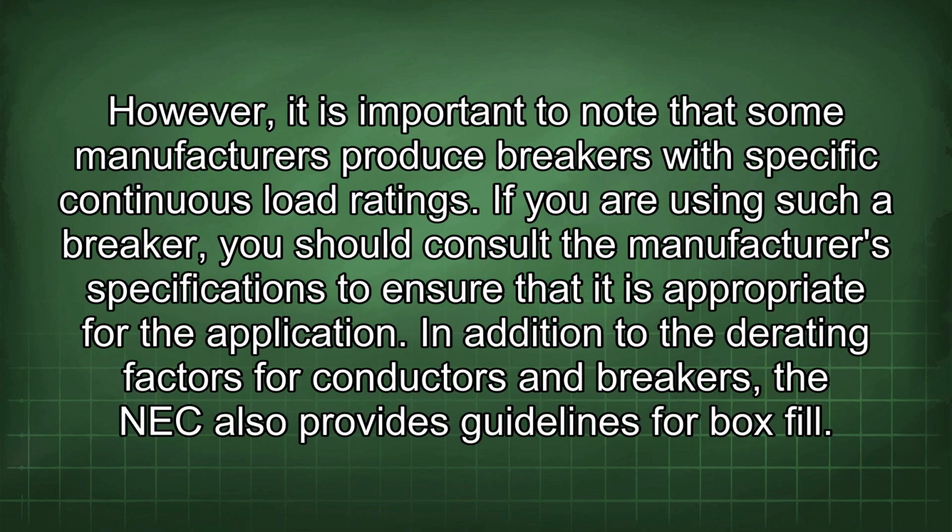However, it is important to note that some manufacturers produce breakers with specific continuous load ratings. If you are using such a breaker, you should consult the manufacturer's specifications to ensure that it is appropriate for the application. In addition to the derating factors for conductors and breakers, the NEC also provides guidelines for box fill.